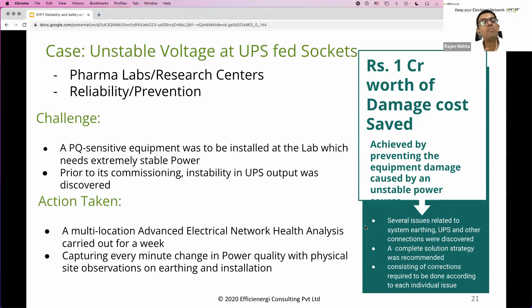We did multi-channel measurements with respect to power quality, earthing, leakages, and ground potentials - at the socket level, at the UPS level, everything simultaneously. You can see actual fluctuations in the UPS output that was prevalent in the network, in the current, and resultantly in the ground potentials also.